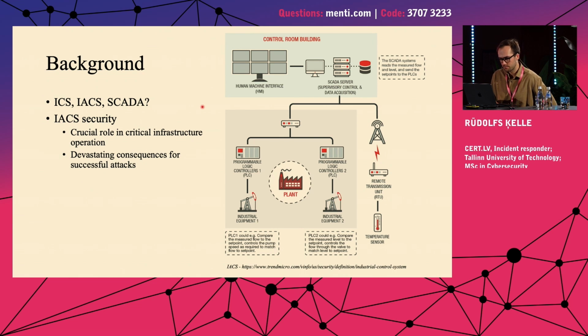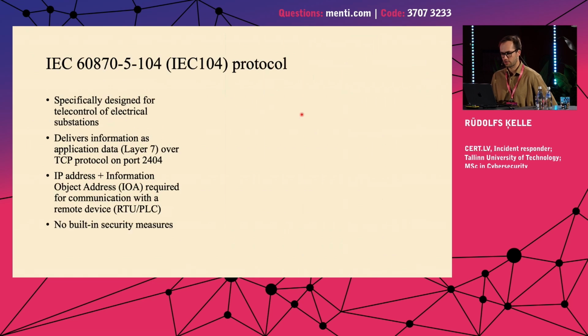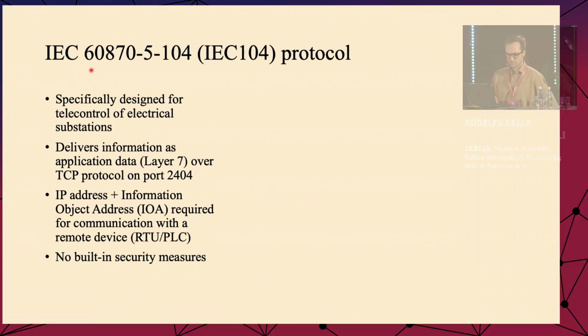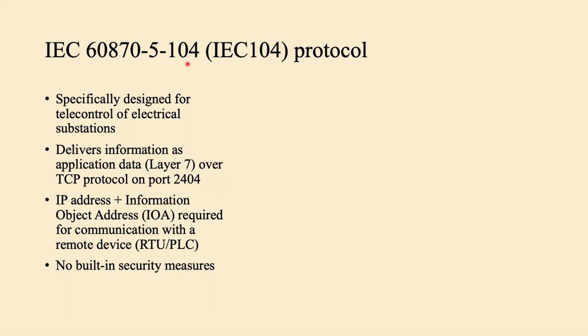Okay, moving on. This SCADA server communicates with RTUs using a protocol, different kinds of protocols, but in our case, we look at just one protocol for this prototype, and the protocol is IEC 60870-5-104, or IEC 104 protocol. Now, this protocol is specifically designed for telecontrol of electrical substations. It sits on top of TCP, so you have all the sessions, and uses port 2404.